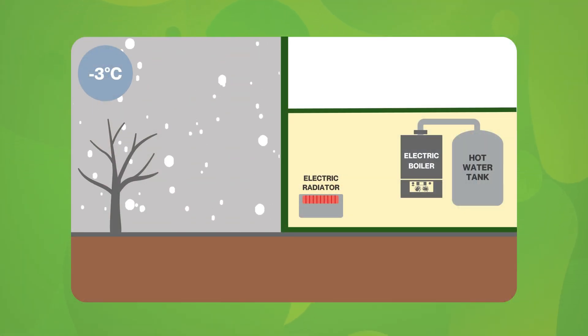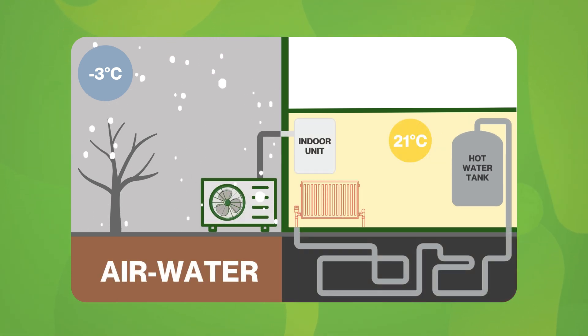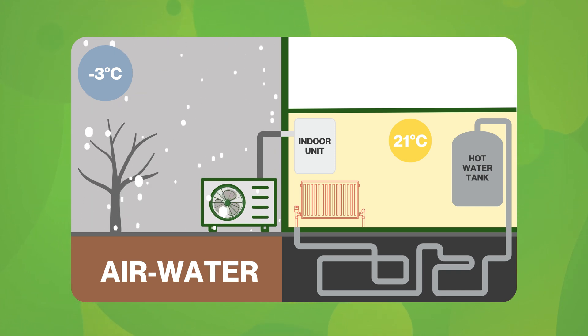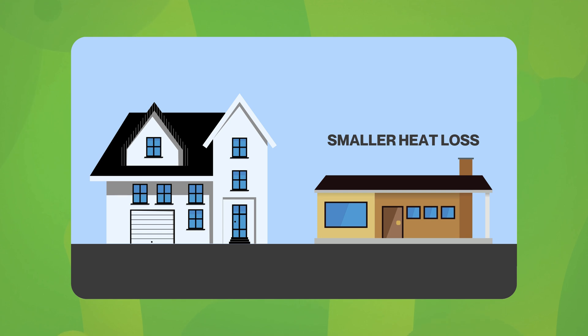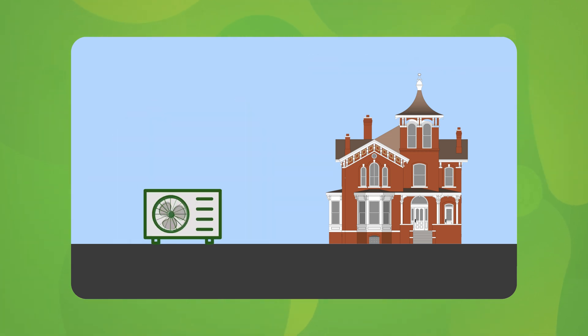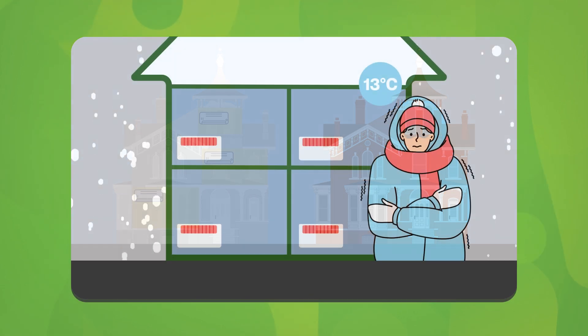For a home to accommodate an air source heat pump, often the pipework and radiators need to be replaced. This isn't the case for every home, but for properties where it is, this means the installation will be more disruptive and expensive. The benefit of an air-to-water heat pump is the system will be designed bespoke to the home, but for some larger homes this just isn't possible. The bigger the house, the bigger the heat loss or energy required to heat it. If you have an older home, this also plays a factor into whether air-to-water heat pumping is possible at all — it may mean you require multiple air-to-water heat pumps at a higher cost, which just isn't practical sometimes. Air-to-air systems offer an alternative and can allow curious customers to dip their toes in renewables without the high price tag. They also create an immediate comfort — you can isolate the rooms of importance, and it is a modular system allowing you to expand it as you please.